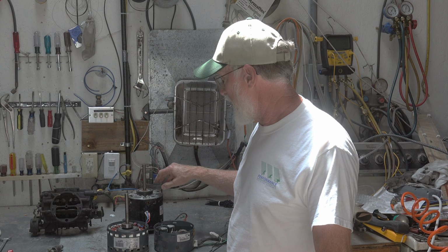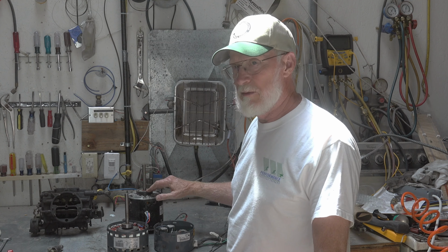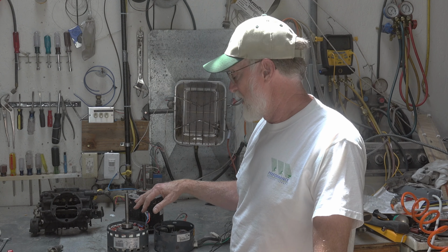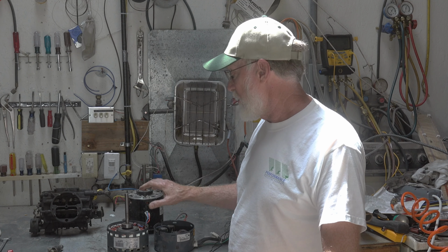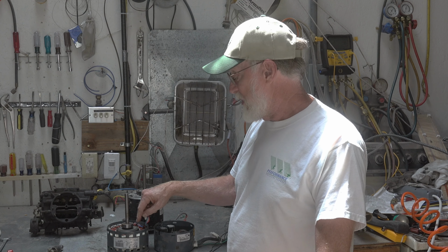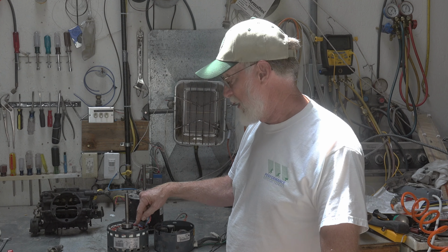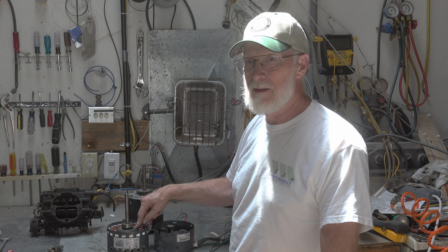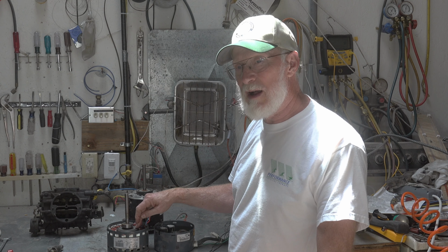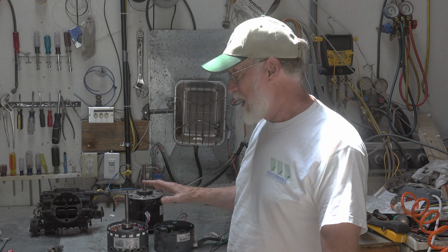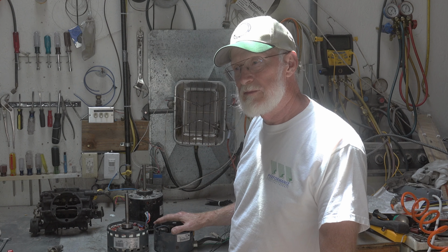I know they all say it's higher. I didn't find them to be a lot higher than what I tested. But if I'm running high speed on this and high speed on this, the draw isn't that much different. But if I lower the speed of this thing, it's amazing. It drops dramatically. Its efficiency stays high, but its speed goes low. So that's what we were looking for. Variable speed in motors.